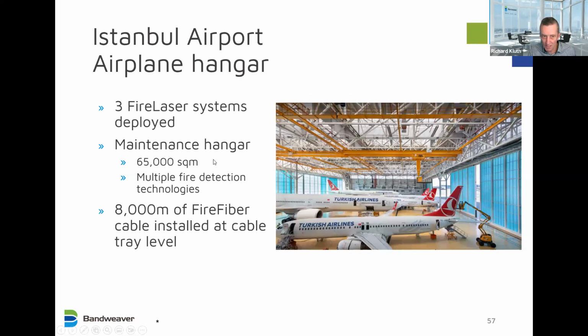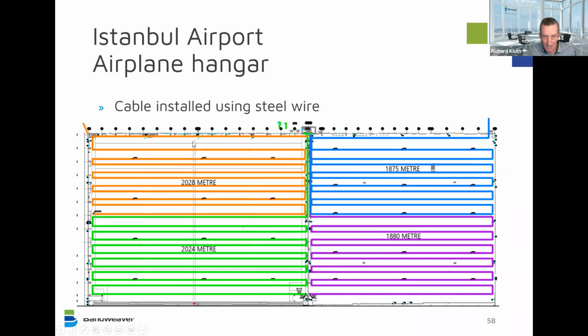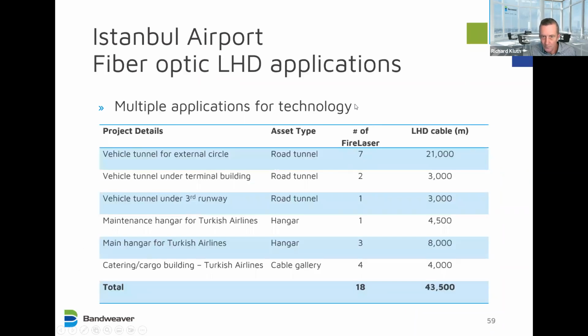This is a very large maintenance hangar, 65,000 square meters, with multiple fire detection technologies. The fire fiber was 8,000 meters of it, installed at the cable tray level. And we can see here the length that's run backwards and forwards in 4 separate zones, installed using steel wire. Also in the airport, the fire lasers are installed in a number of different road tunnels, 2 separate hangars, different cable galleries, for a total of 18 fire laser systems at the time of writing. It's still going up. So, fantastic use of technology throughout the airport.